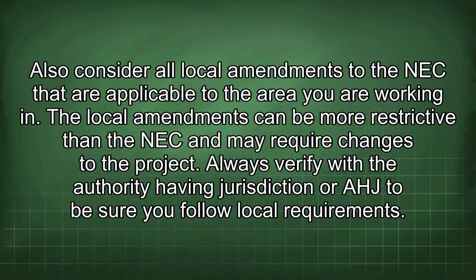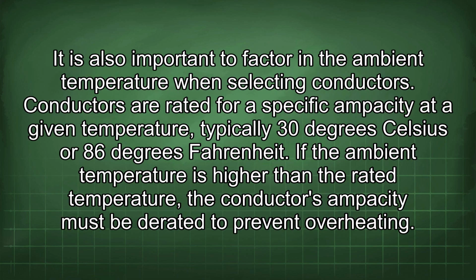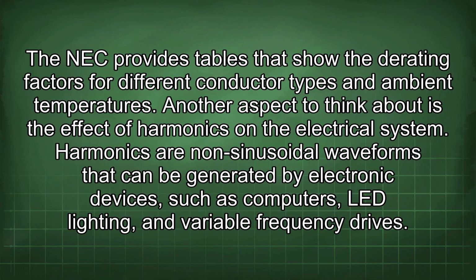Also consider all local amendments to the NEC that are applicable to the area you are working in. The local amendments can be more restrictive than the NEC and may require changes to the project. Always verify with the authority having jurisdiction, or AHJ, to be sure you follow local requirements. It is also important to factor in the ambient temperature when selecting conductors. Conductors are rated for a specific ampacity at a given temperature, typically 30 degrees Celsius or 86 degrees Fahrenheit. If the ambient temperature is higher than the rated temperature, the conductor's ampacity must be derated to prevent overheating. The NEC provides tables that show the derating factors for different conductor types and ambient temperatures.